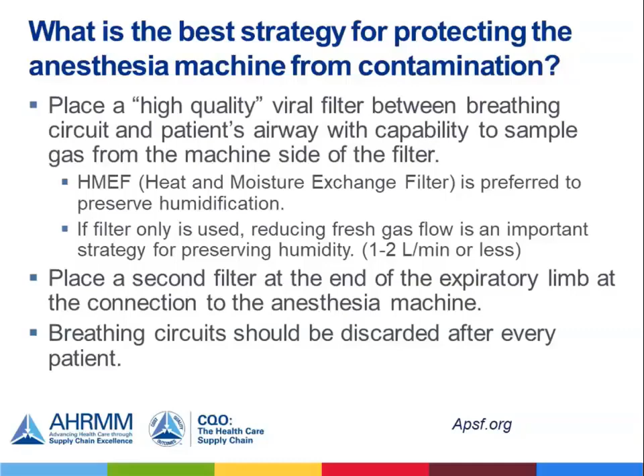In particular, the Anesthesia Patient Safety Foundation published a diagram that you see on this slide, which shows a high efficiency moisture trapping filter at the end of what we refer to as the Y, which you can see there, and the gas sampling that I spoke about before, which is on the machine side of the filter to avoid contamination of our machine. The additional filter, the high viral efficiency extraction filter, is located on what's referred to as the expiratory limb, which would then protect further the anesthesia machine from contamination with the virus particles.